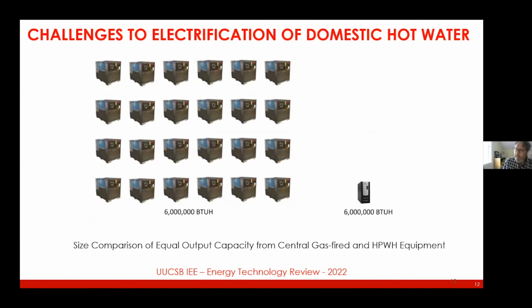We have some challenges with regard to the electrification of either space heating or domestic hot water. This is more or less to scale, showing the size of a 6 million BTU an hour gas-fired boiler and 6 million BTUs an hour of air source heat pump capacity. And while the relationship between the space requirement and the first cost is not completely linear, there is a significant relationship. So clearly this alternative is going to cost many times more in first cost than this alternative, and we need to overcome that issue.